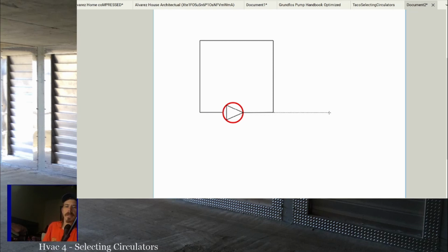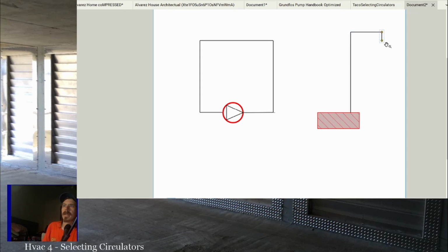Whereas if you're talking about something like a condensate pump, right? This pump, just draw a rectangular box for a condensate pump. It has to pump up, over, and out, right? So since it's going out and that side's not coupled to the pump, it has to actually counteract that pressure of pumping up. But when you're talking about a circulator, it's just going around in a circle. So the pressure is going to force itself down and up, so it cancels itself out. So when they talk about feet of head when it comes to a circulator, the actual rise of the piping doesn't matter because it's one big loop. Does that make sense?